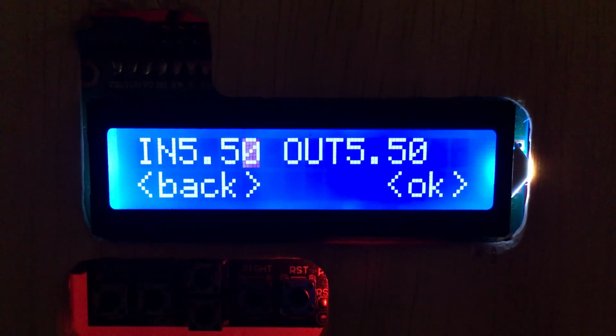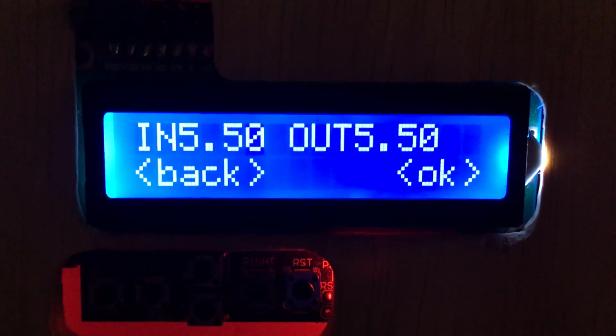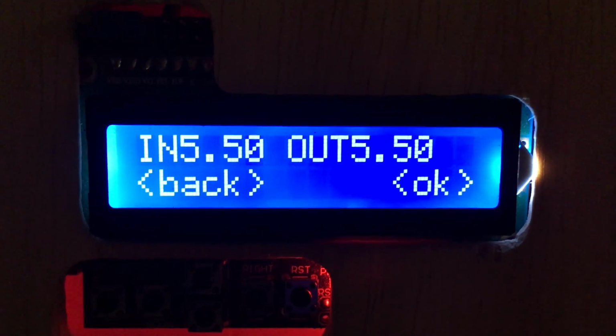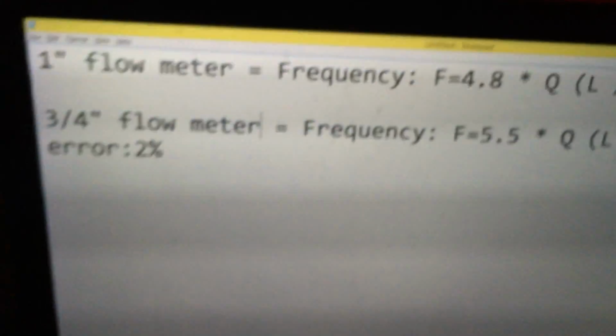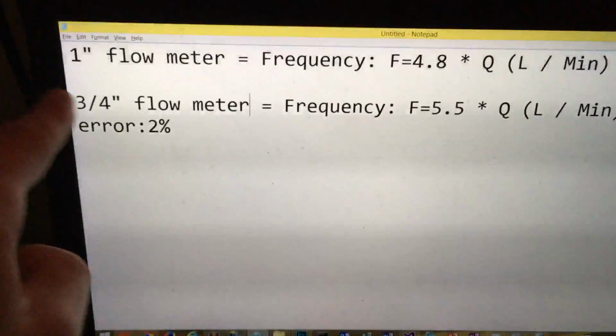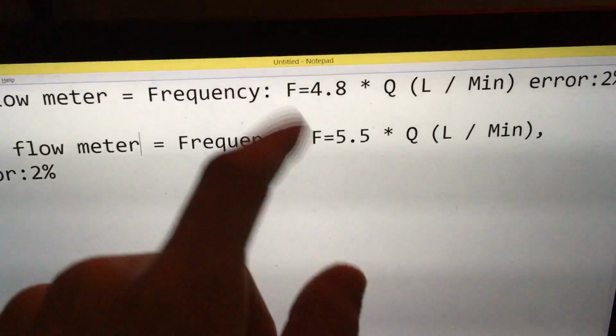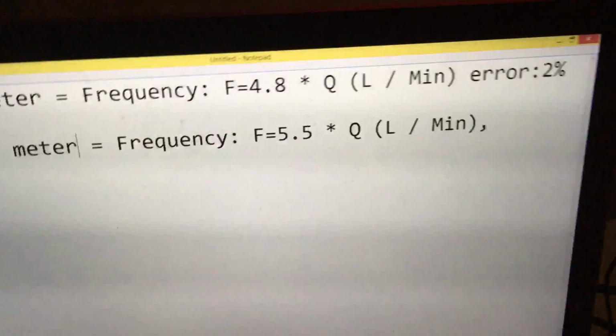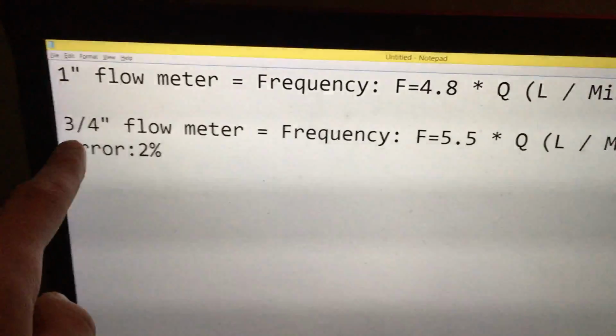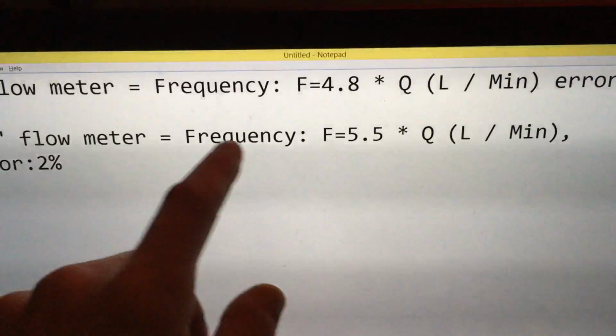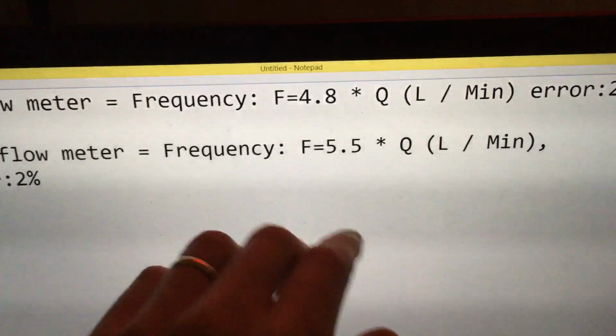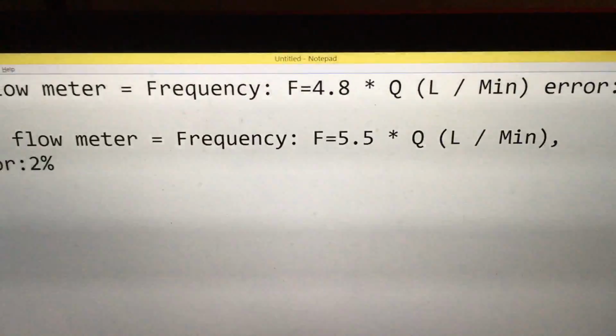The calibrations can be found with the specs that come with the actual flow meters, or you can find them online. They look something like this. So for our 1-inch flow meter, we have a frequency of F equals 4.8, yada yada yada. We're interested in that 4.8 number. And for a 3/4 flow meter, you're going to find the specs say something like frequency F equals 5.5.